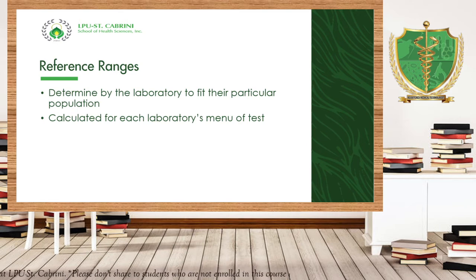Number one reason is the establishing of the reference range that they have. Another is the principle of the machine that they are using. And lastly is the validation of their reference range. That's why you cannot compare the reference range of each hospital because they are not the same. And that is calculated for each laboratory's test menu.